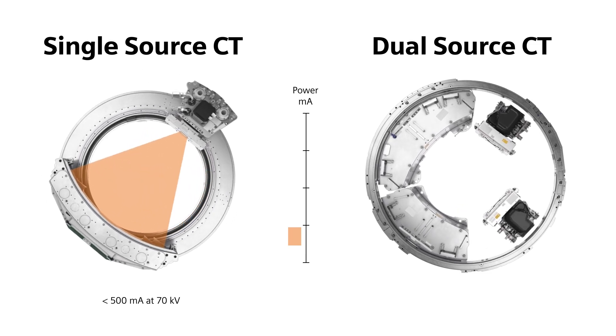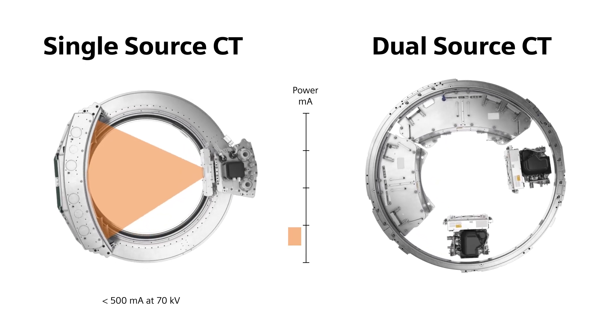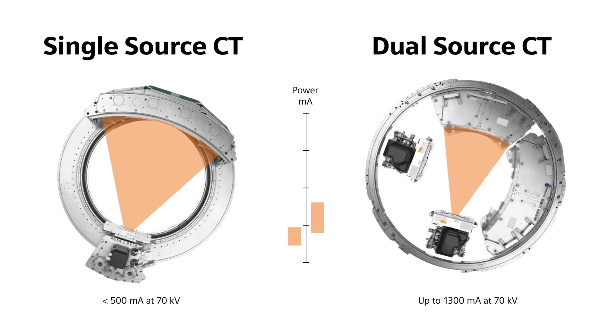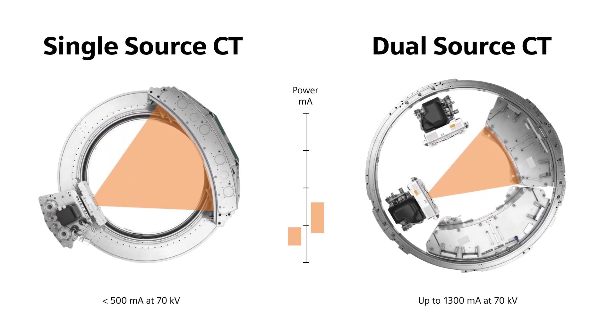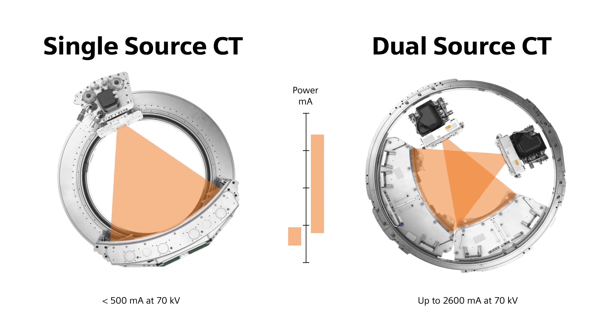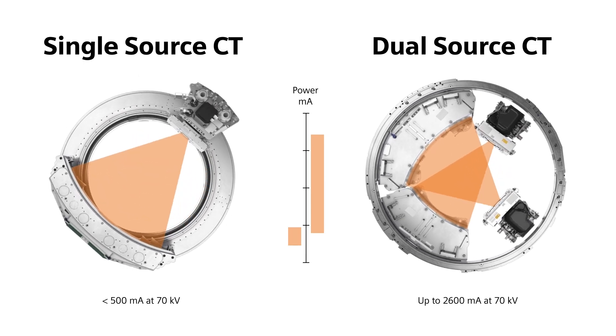Dual source CT scanners sport two extraordinarily powerful tubes, each delivering up to 1300 mA at 70 kV. The output of both tubes can even be combined — you can turn up the power all the way to 2600 mA if necessary.